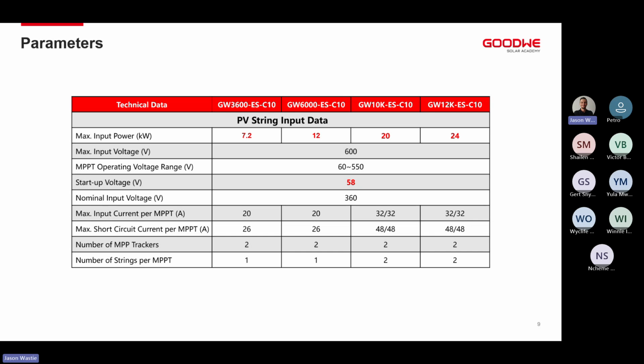Secondly, if the PV starts operating at 60 volts, that means we get an extra PV production time of maybe 5 minutes in the morning and 10 minutes in the afternoon, and that can be quite beneficial. Again, at 60 volts, we're probably not going to be able to run loads, but it can start trickle charging the battery at an earlier time. If we're getting an extra 5 minutes of charge in the morning and 10 minutes in the evening, call it 15 minutes over a day, add that over 5 years of the inverter's warranty, and see what the proposal would look like.